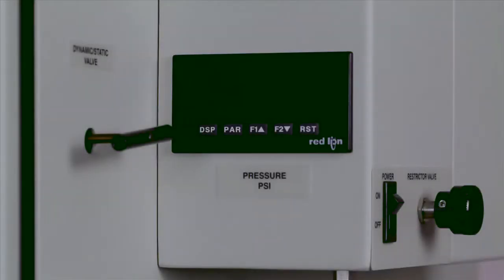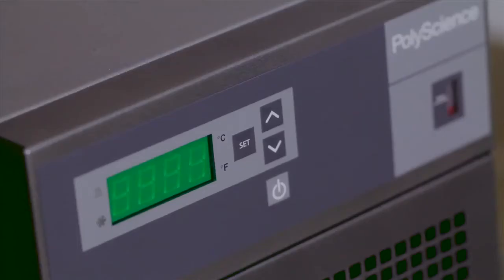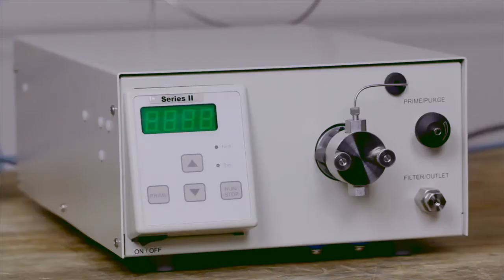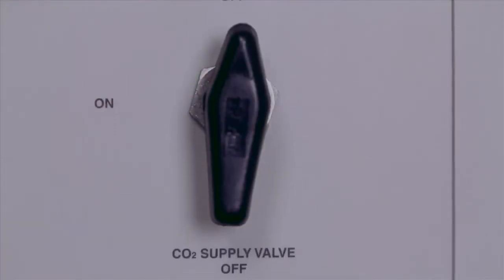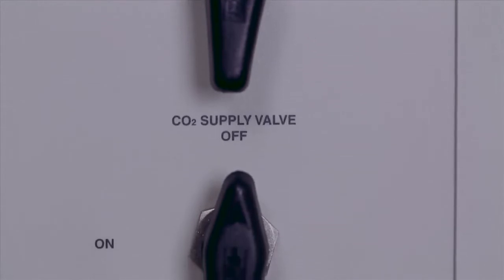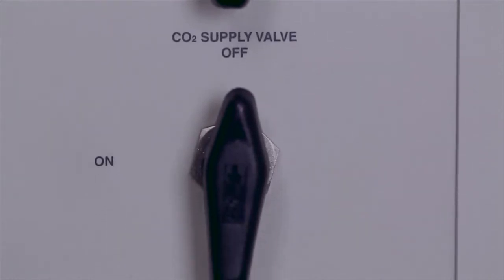Startup and operation. The following steps should be followed to ensure successful startup of the SFT-150. Make sure that all power switches on the SFT-150, chiller, and optional co-solvent pump are turned off. Additionally, the pump air supply and the CO2 supply valves must be in the off positions.